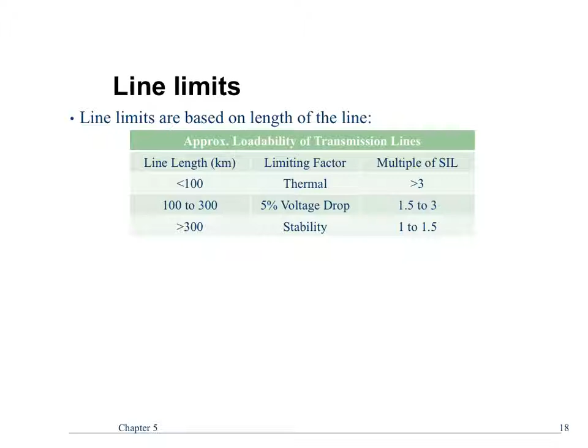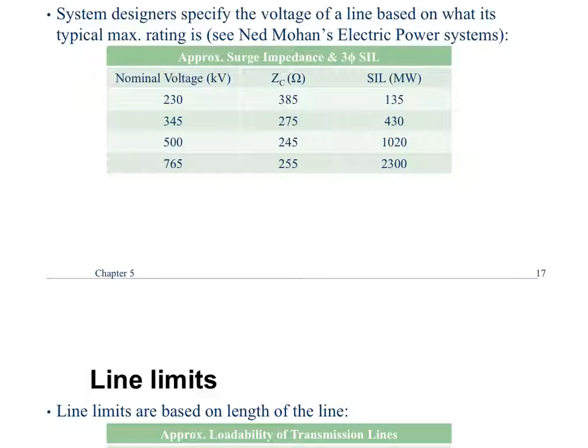And then if you're getting to a longer line, now we're limiting in terms of stability, and that has very little to do with voltage ratings and SIL. That has to do with the fact that I can only move so much power across the line before my system is going to respond slowly, based on the length of the line. So in Maine, a 345 kV line, there are no long lines in Maine. They're all 80 to 90 miles or less. You can run it at up to 3 times 430 megawatts. So you can get 1,300 megawatts, just about the max for just about any 345 kV line in the state of Maine.